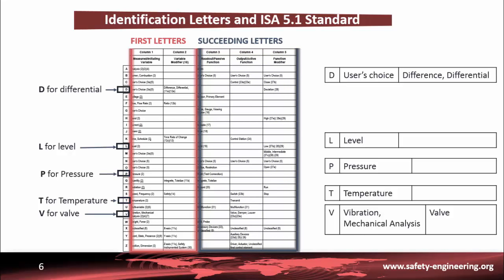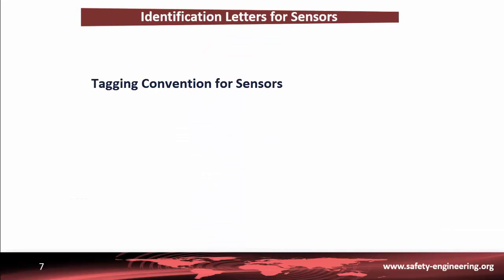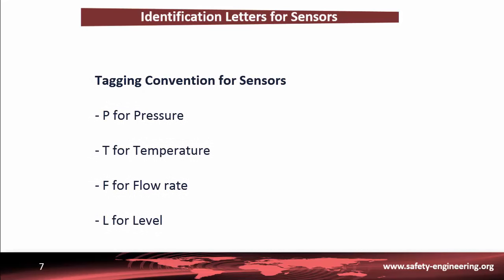Now we are going to present some examples to better understand the tagging conventions for control loops. Firstly, we will explain the tagging convention for sensors. The primary sensors encountered in the chemical industry are pressure (P), temperature (T), flow rate (F), and level (L). These first letters can be associated with other letters, like E, which means the sensor alone — the primary element. The output of the primary element is referred to as the raw signal, and the type of raw signal depends on the kind of sensor.